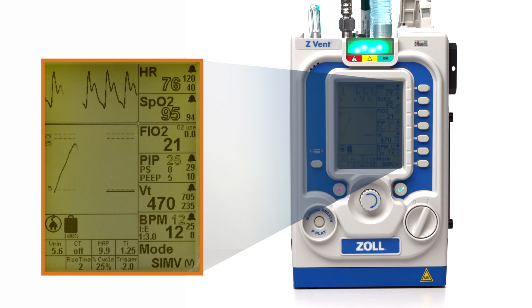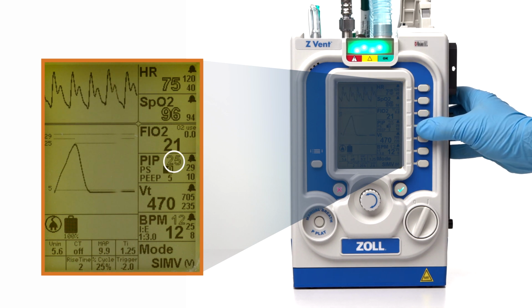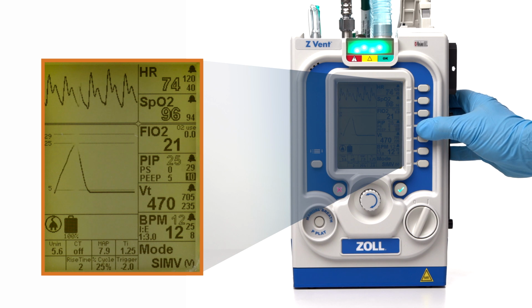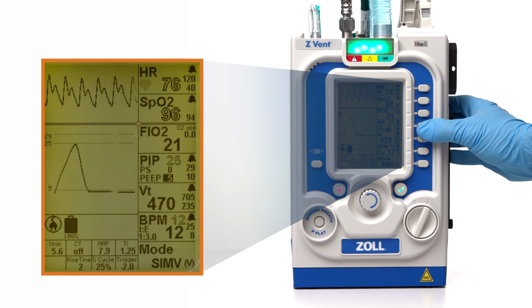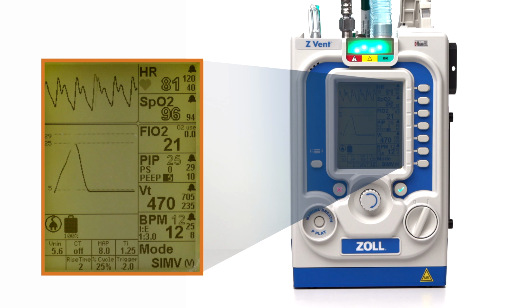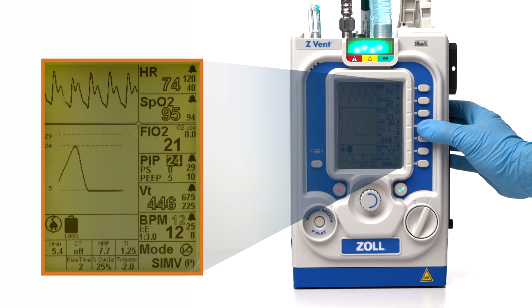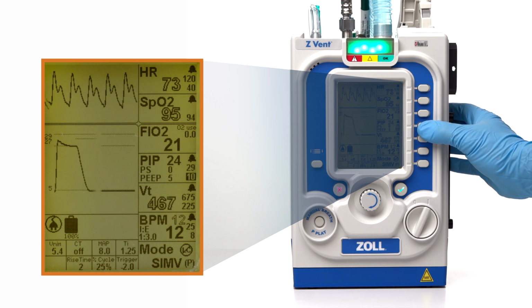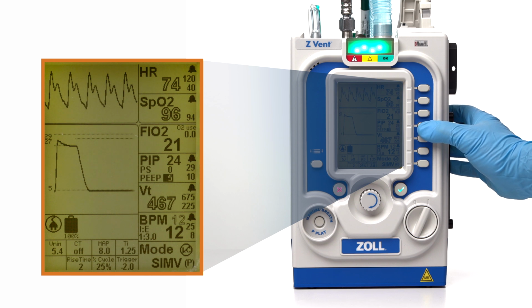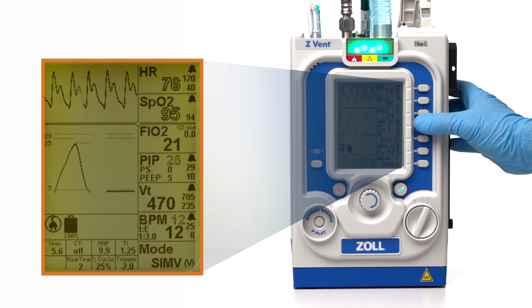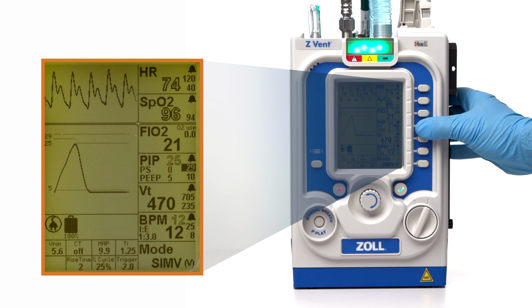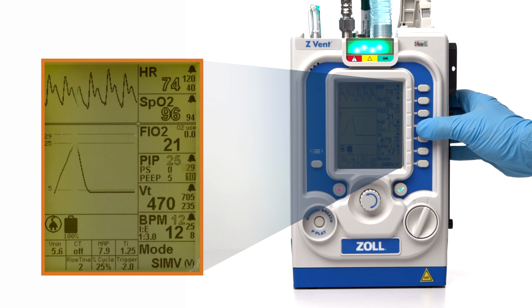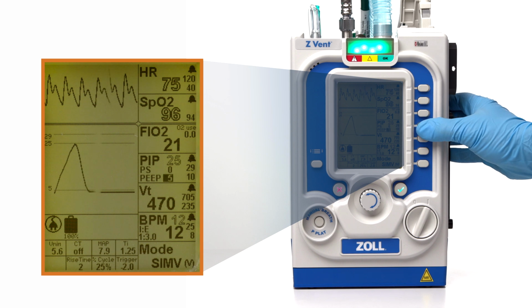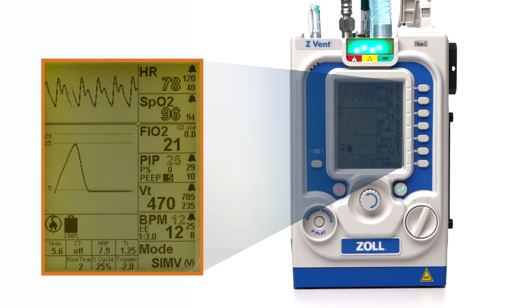When operating in a volume-targeted breathing mode, PIP is a calculated value and will display as an outlined number that cannot be changed. In pressure-targeted breathing, press the parameter button once to change the desired PIP, twice to change the high pressure limit, 3 times to change the low pressure limit, and 4 times to change the PEEP. In volume-targeted breathing, press the parameter button once to change the high pressure limit, twice to change the low pressure limit, and 3 times to change the PEEP value.